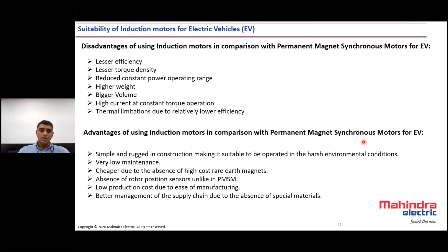There are methods to improve the efficiency of induction motors, the conventional ways where we use low loss silicon steel laminations to reduce the constant losses. Some of the manufacturers are going with thinner laminations, 0.25 mm laminations, to bring down the eddy current losses and also get that benefit on the constant loss. Optimization of slot fill factors to reduce the variable losses, which is nothing but the I-squared losses. Higher core lengths and diameters offer us an option where we can go for improved efficiency. Design optimization with adequate slot configurations and profiles, the same as what we saw in one of the comparisons.